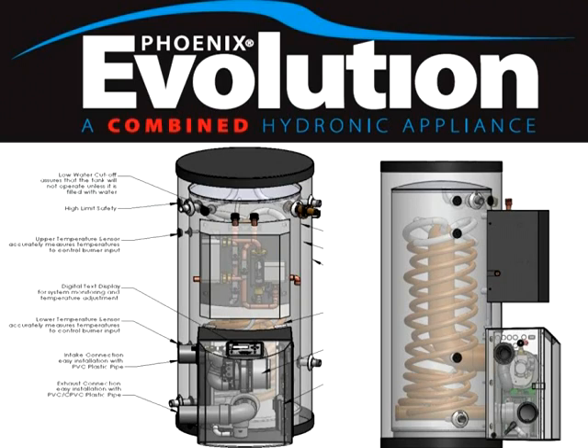So when you look at this unit and why we're calling it an appliance, in essence, you are getting a condensing boiler, an indirect water heater, and the mechanical piping all in one package. And you'll see that the mechanical piping and controls and everything have been greatly simplified in this sort of integrated design.